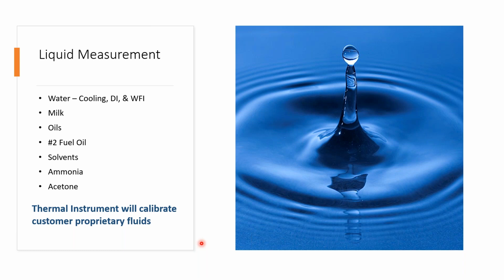So even if, let's say in a 60-inch pipe, we put the insertion probe through the bottom of the pipe where the fluid was sitting, if it's only half full, the insertion probe is still going to read it like it's full. The calculation is based on a full pipe ID, and if it's half full, it still sees the flow, but your calculations are going to be off by 50% for that period. Correct. Got it.